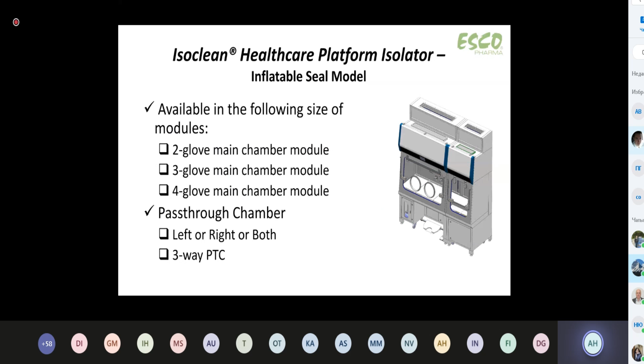Okay, I will show you some of the features here. We have modules: 2 glove, 3 glove, 4 glove, same thing here. You can have a pass-through chamber on the left, on the right, or 3 ways. 3 ways means that if this was the pass-through chamber, you can have one way, left, to connect to this isolator, and right to connect to the other isolator. So the pass-through will be in the center. It's possible. This will be some of the parts.